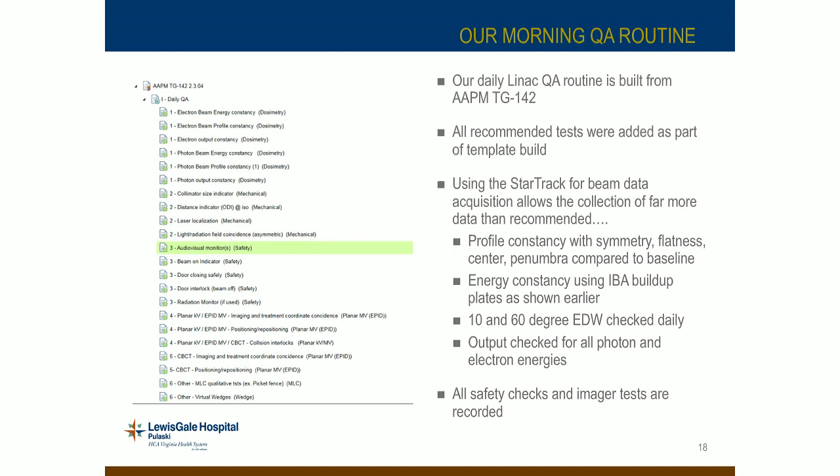We use a StarTrack to acquire the beam data, and this allows us in the morning to take a whole lot more data than is actually required for morning QA. For example, part of our morning QA, we do profile constancy. It's got symmetry, flatness, center, penumbra, and all of these are compared to a baseline. The energy constancy plates, we use that to make sure the energy is where it should be on the machines every morning.